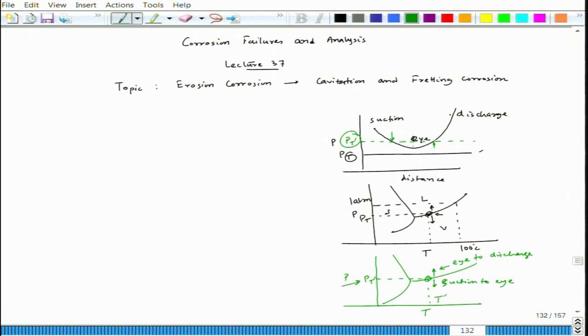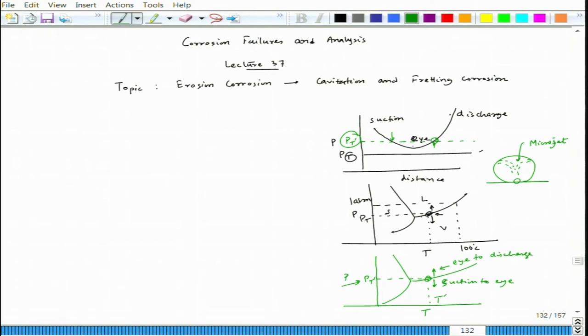At that point cavitation occurs: the bubble collapses such that a micro-jet hits the surface at very high speed, generating a pressure close to around 500 MPa. That can deform the surface and, in passivating metals, remove the passive layer. Before the next bubble forms, the metal can repassivate if it is strongly passivating, but by that time there is a small amount of material loss — that is the loss of metal through cavitation.